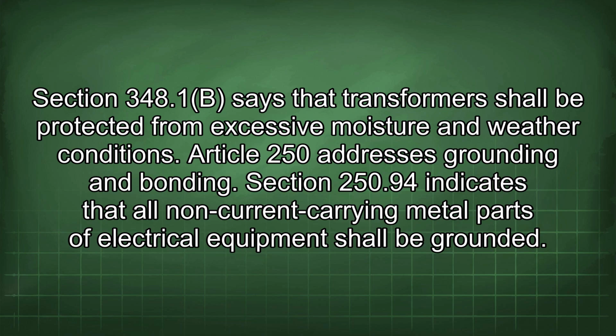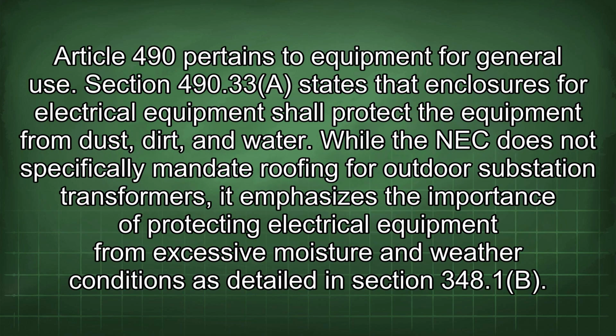Article 250 addresses grounding and bonding. Section 250.94 indicates that all non-current carrying metal parts of electrical equipment shall be grounded. Article 490 pertains to equipment for general use. Section 490.33 states that enclosures for electrical equipment shall protect the equipment from dust, dirt, and water.